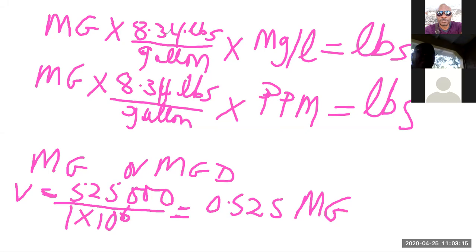Million gallons per day, or MGD, is equal to the same 8.34 pounds per gallon, the weight of a gallon of water, by the dosage, whether in milligrams per liter or ppm, would be pounds per day. It's the same thing. All right? So have it there. I'll go back to it and convert it just now, but let's work out the problem now.